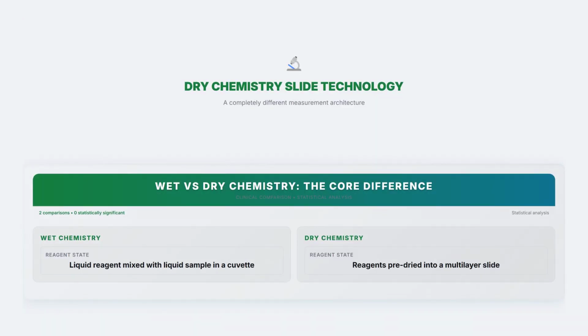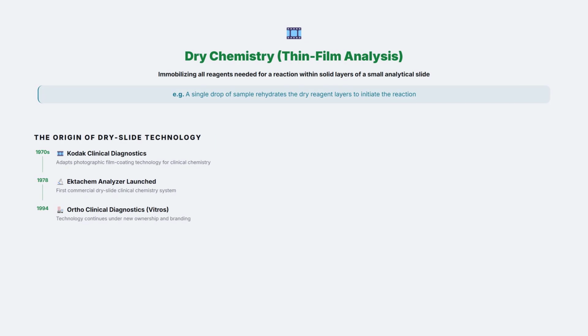Every wet chemistry analyzer you've worked with mixes liquid reagent with liquid sample in a cuvette. Dry chemistry technology throws that entire model out. No reagent prep, no cuvette, no liquid reagent at all. A single drop of sample lands on a credit card-sized slide, and the reagents are already there, dried into the slide itself, waiting.